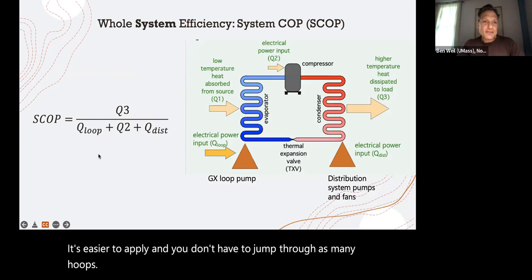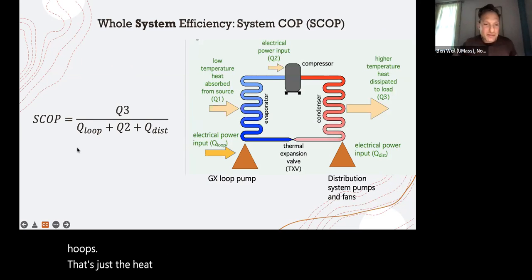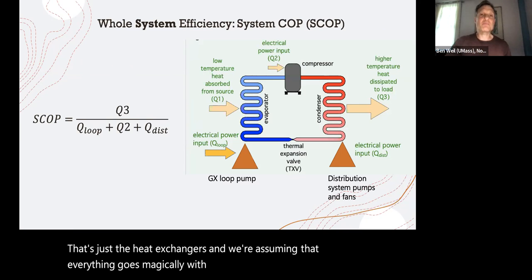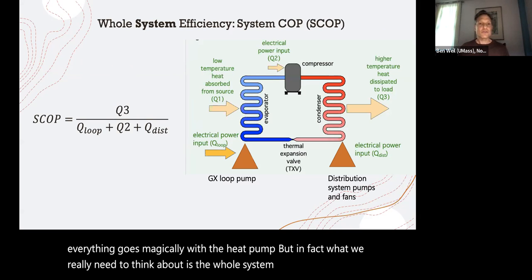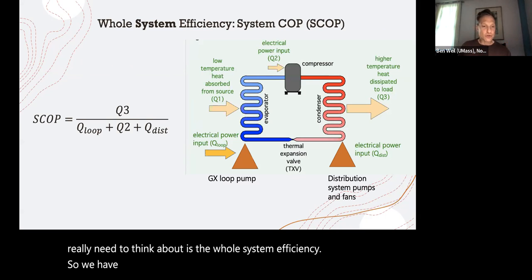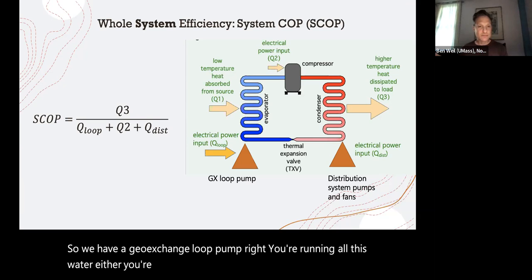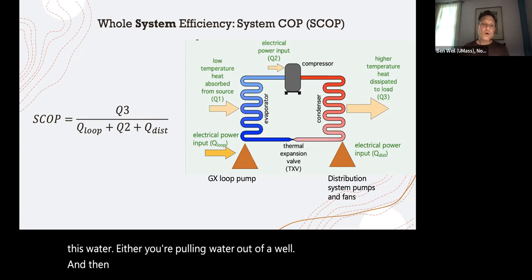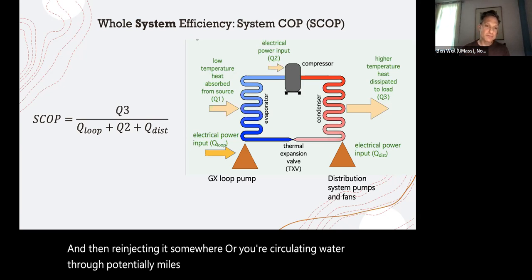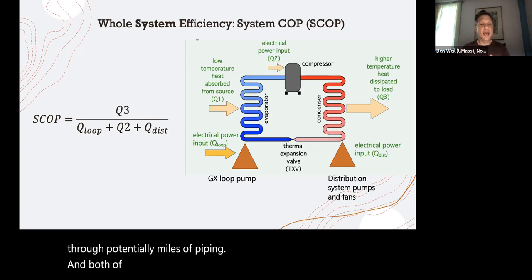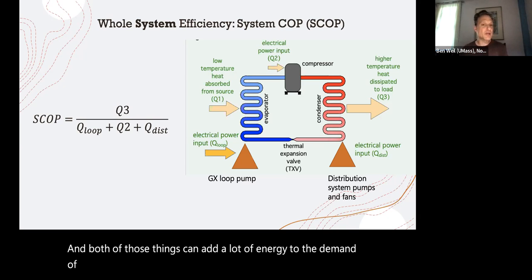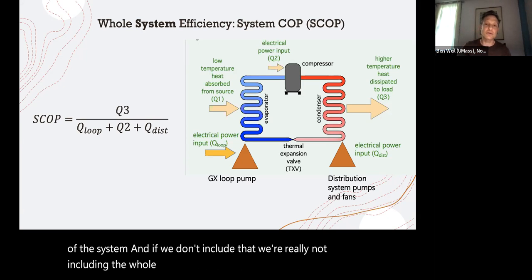So that's just the heat exchangers, and we're assuming that everything goes magically well with the heat pump. But in fact, what we really need to think about is the whole system efficiency. So we have a geo-exchange loop pump, right? You're running all this water. Either you're pulling water out of a well and then re-injecting it somewhere, or you're circulating water through potentially miles of piping. And both of those things can add a lot of energy to the demand of the system. And if we don't include that, we're really not including the whole system and how it works.